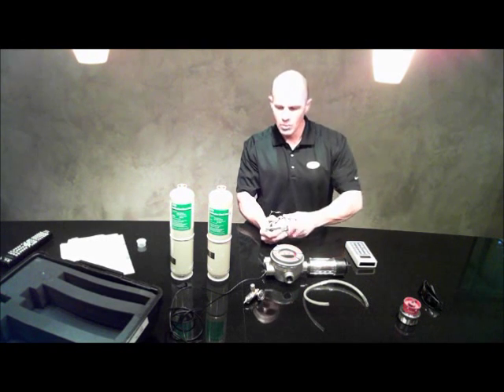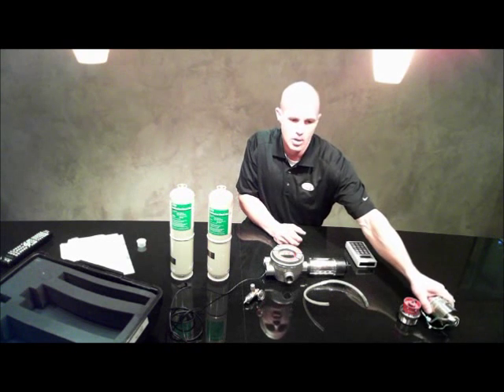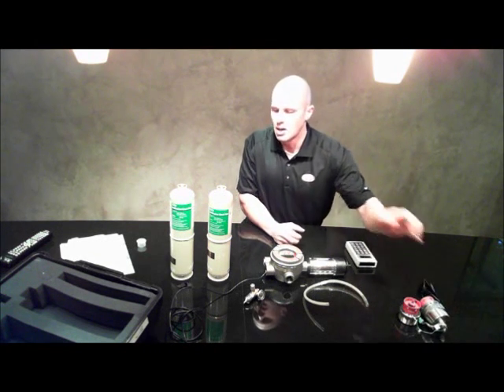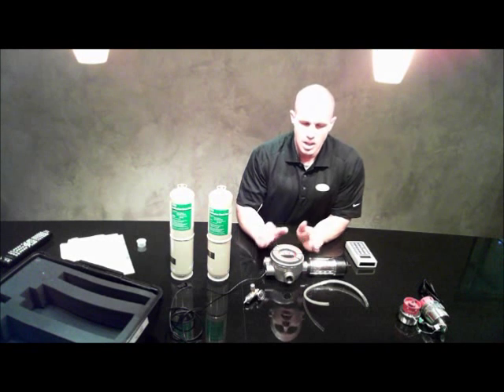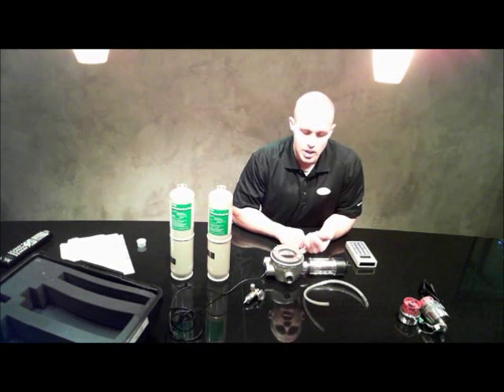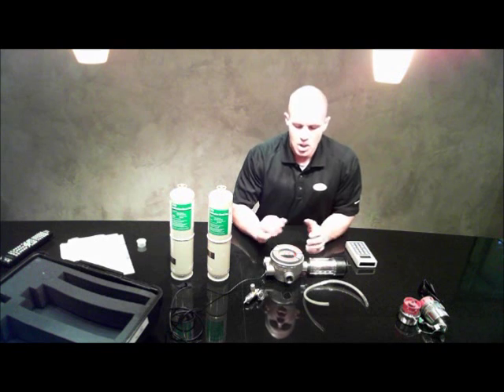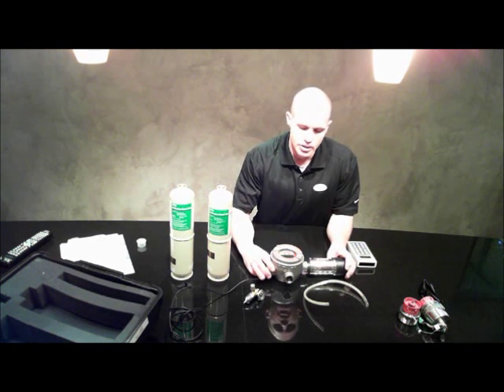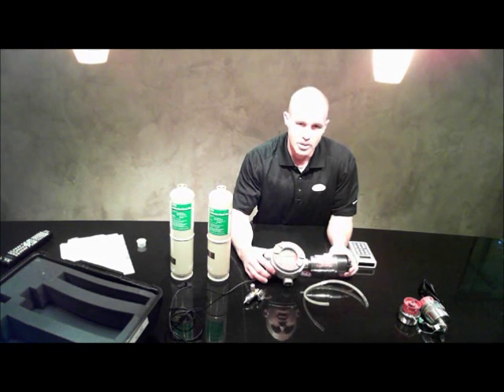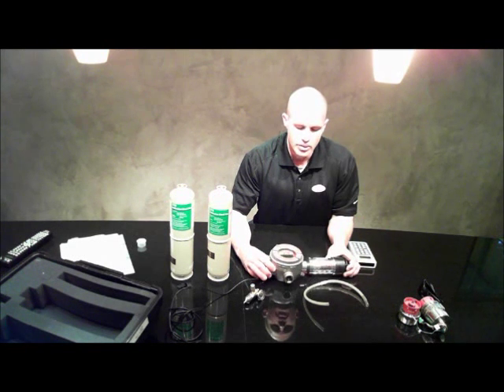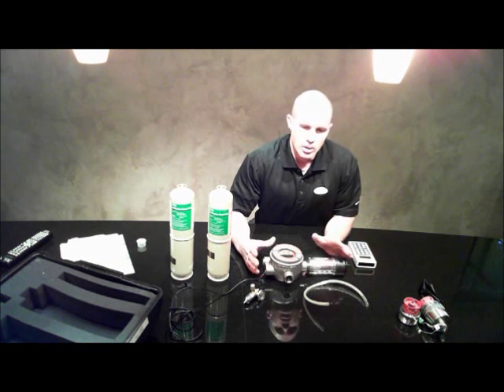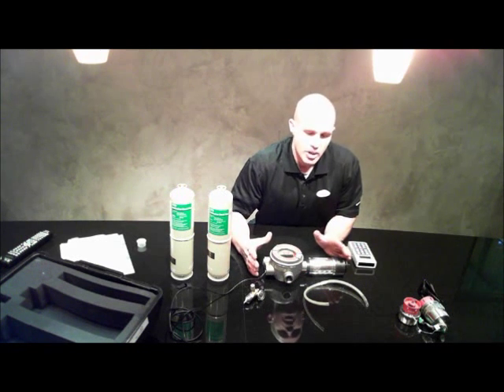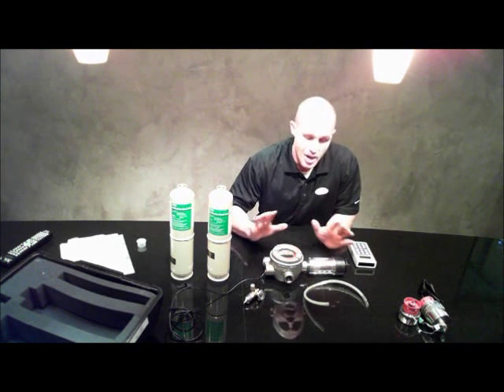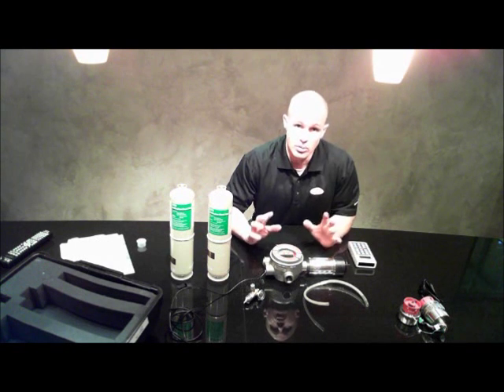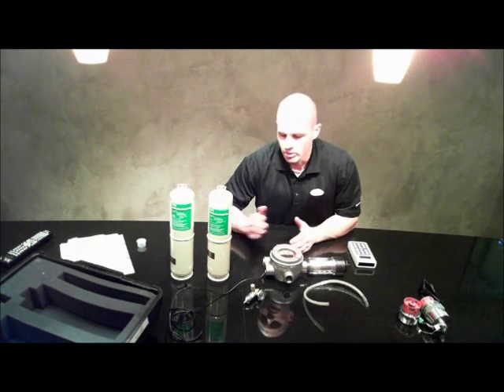So what I want to do today is show how to do a calibration on a gas monitor, and I'm going to show you how to do both an initial calibration and a standard calibration. Right now this monitor is showing 9% LEL, so there's something wrong with the sensor. We're going to do an initial calibration, pretending like it's a brand new sensor just being put into service. We'll do an initial calibration, then I'll repeat it, just going through a standard calibration.